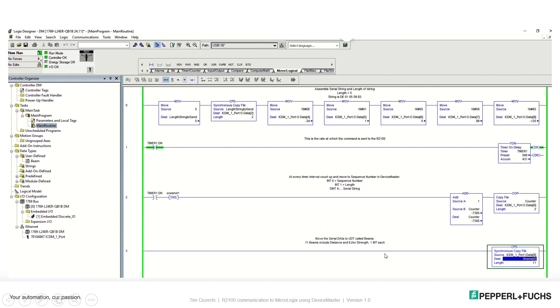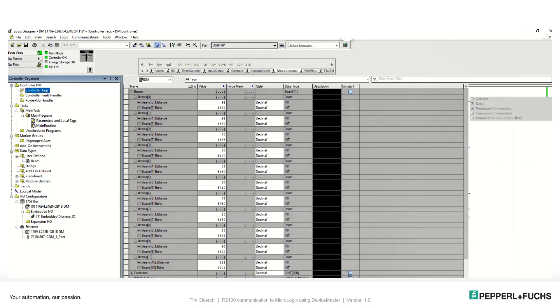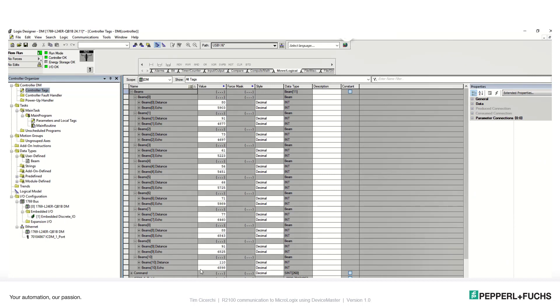Now I just want to show you a quick live demonstration. You can see my four rungs: the command, the timer firing at half-second increments, counting up by one each time. Each time it fires, I take the received data and populate my 11 beams with distance and echo values. If I put my hand over it, you can see it's at 90 millimeters. Now I'm slowly moving my hand away — it's going up higher and higher, now at 496 millimeters. You can also see in the Ethernet tree there's no yellow triangle, so you know the communication is working properly.